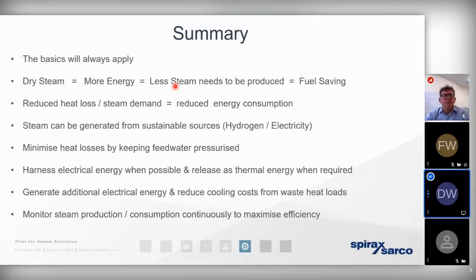We know that it's going to be possible to move towards a solution where we can generate steam from those existing traditional steam boilers simply by retrofitting the fossil fuel burners out for an alternative source of fuel. For example, moving towards a hydrogen burner or moving towards an electrical heater element. If we can move towards a pressurized deaerator, then we're going to add a significant amount of cost savings that can be realized from a number of different areas.